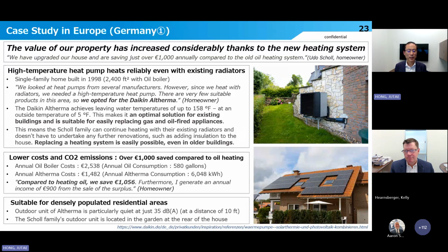But there are very few suitable products, so they opted for Daikin high temperature Altherma. Second, low cost and CO2 emissions. Their annual oil boiler cost was around 2,500 euro with an annual oil consumption of 580 gallons. Now, their annual Altherma cost is around 1,400 euro. This means compared to heating oil, they are saving over 1,000 euro annually.